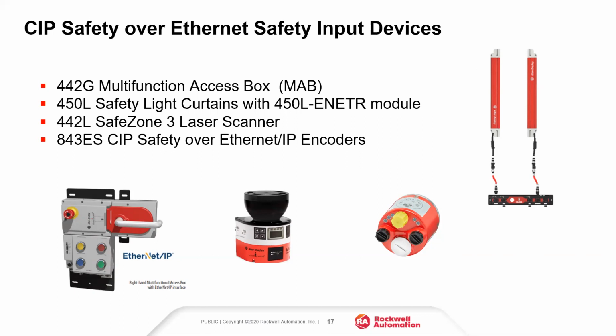The next input device is the 450L safety light curtains. Rockwell's the first one to introduce a light curtain on Ethernet. This is done with our standard 450L light curtains, either the basic or the enhanced light curtains, and then you simply connect those to the 450L EN ETR module, and that brings that back over CIP Safety over Ethernet. So you're using standard patch cords from the light curtains to the module, and then standard Ethernet connections back to the processor or to the network.